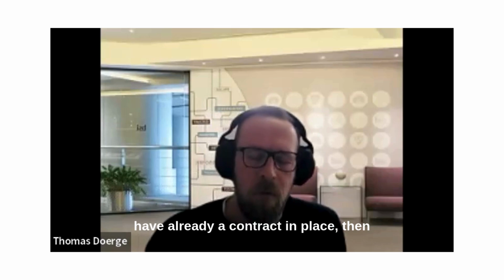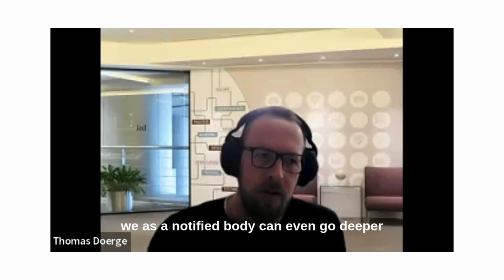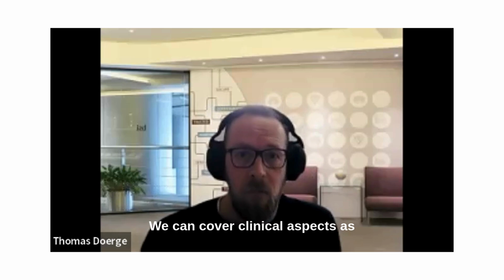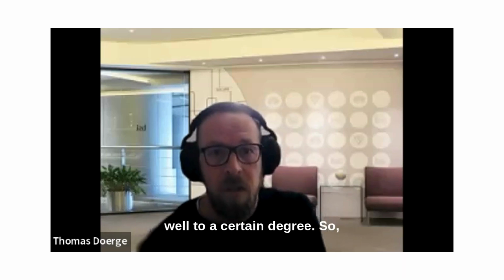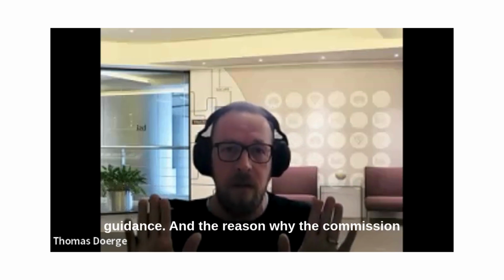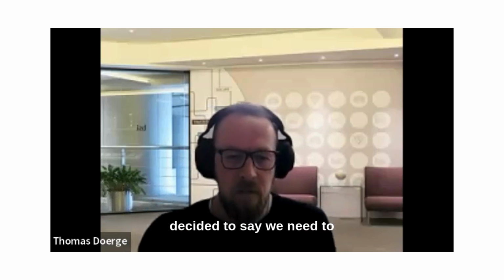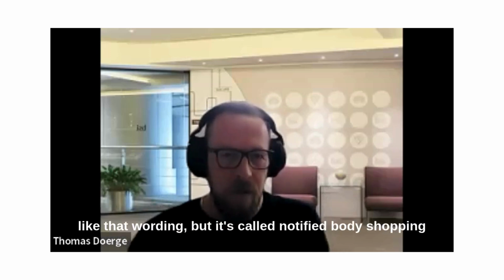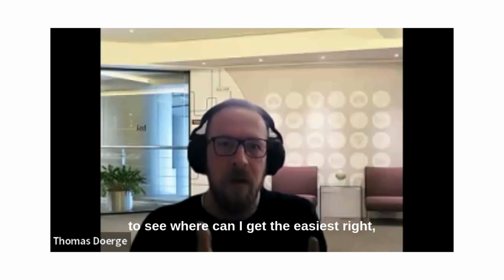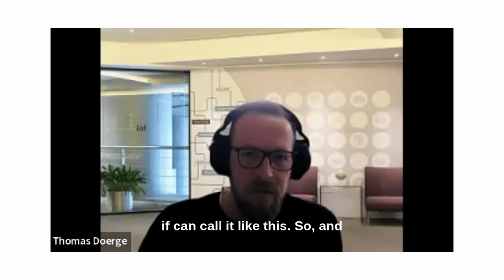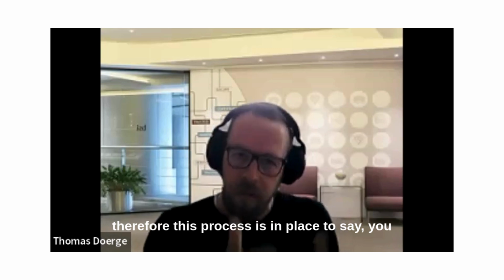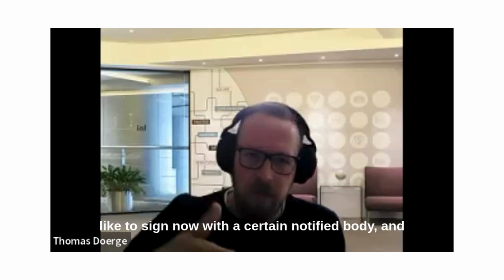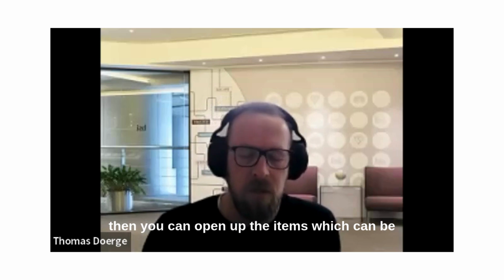If you already have a contract in place, then we as a notified body can go deeper into your technical documentation. We can talk about technical aspects and details there. We can cover clinical aspects as well to a certain degree. So I can just encourage you to read that guidance. The reason why the Commission decided to limit the topics before you have a contract in place is to avoid, I don't like that wording, but it's called notified body shopping, to see where I can get the easiest, if I can call it like this. Therefore this process is in place to limit things before you have a contract, and then we open up. It's up to you as a manufacturer to say, I would like to sign now with a certain notified body, and then you can open up the items which can be discussed.